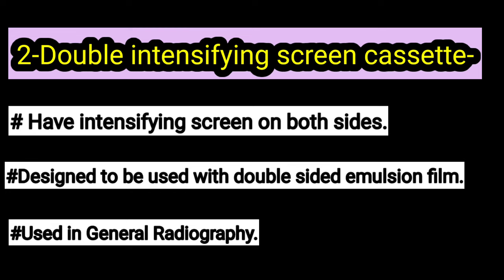The double screen cassettes have two intensifying screens, so they use double-sided emulsion film. They are used in general radiography, while single intensifying screen cassettes are used in mammography. As you can see in this image, this is a double screen cassette with two intensifying screens and double-sided emulsion film.